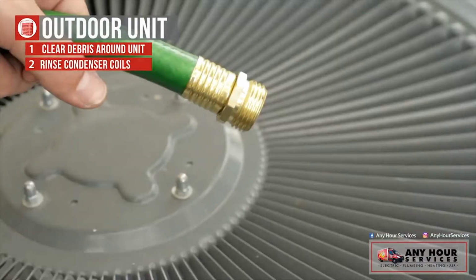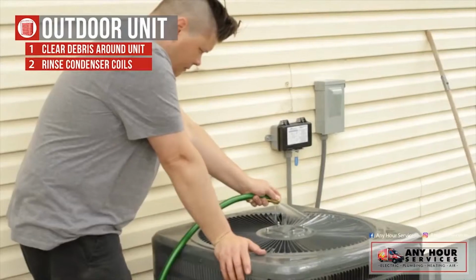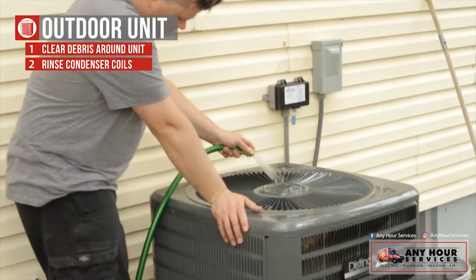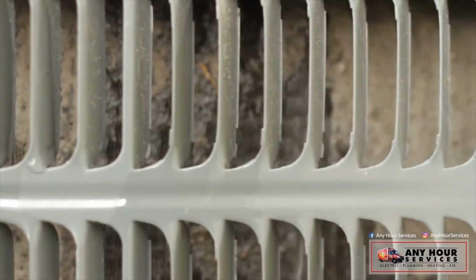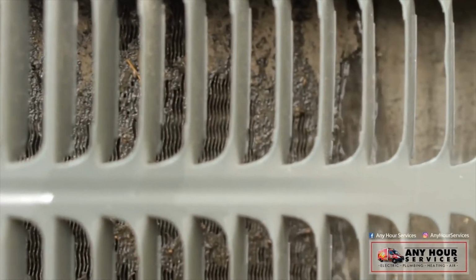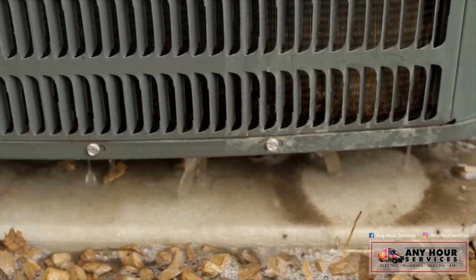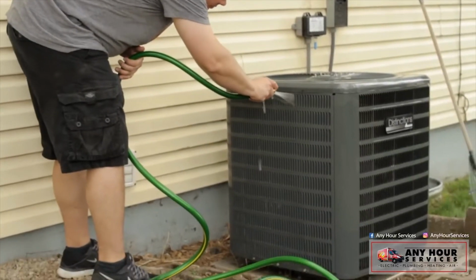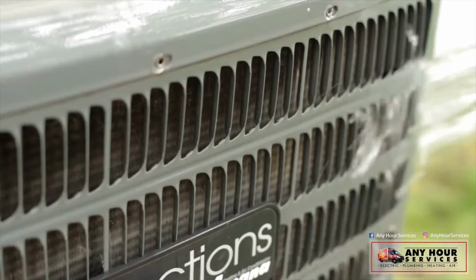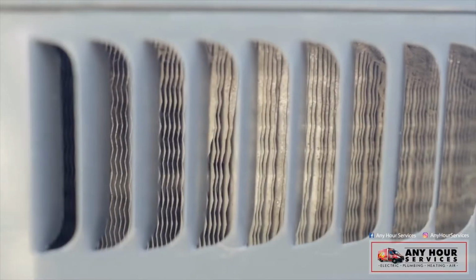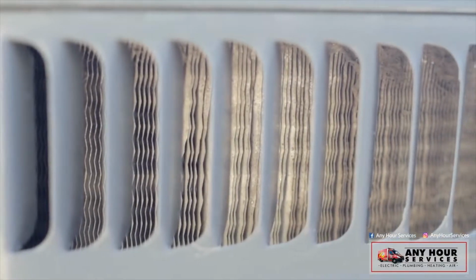Take your garden hose and rinse off the coils. Reach what you can with the garden hose and spray from the inside out. Let the water flow down the coils for a while until it looks like you've gotten all the dirt off. Then spray off the debris you see on the outside. The fins on the unit are very fragile. Be careful that you don't bend them over.